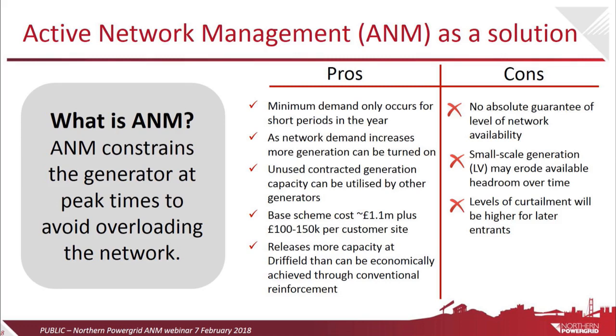What it does is it takes advantage of higher demands on the network and allows more generation to run, and that frees up headroom that was previously untapped, and in this case, initially at least, we only expect active constraints during the summer months when demands are at the lowest. However, it doesn't come without some drawbacks. For instance, there are no guarantees for availability, as we don't control what the existing demand does. Small scale generation, for example, domestic solar, may erode the headroom over time, and the later you join the scheme, the higher the level of curtailment you should expect to be subjected to.